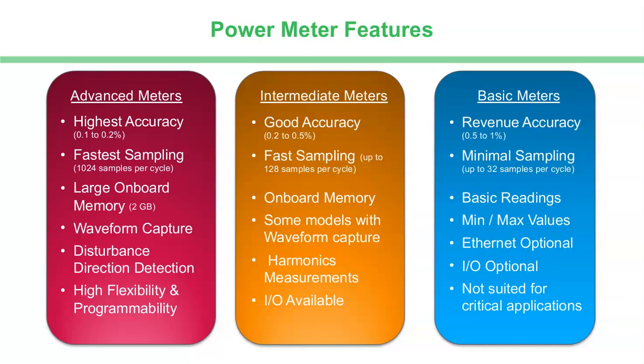Anything less than that, if you were challenged on the readings or the value, you may not be able to say, look, here, this meter is accurate enough and it is capable of standing up to scrutiny. So, you know, you want 1% or better for energy, and as I said, you want to have higher accuracy where you need it.